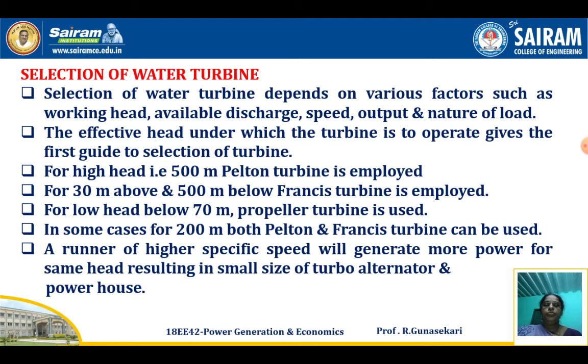Already we studied the characteristics of water turbines and the governing of water turbines. Now selection of water turbine. The selection of water turbine depends on various factors such as working head, available discharge, speed, output and nature of the load. The effective head under which the turbine is to operate gives the first guide to selection of turbine.